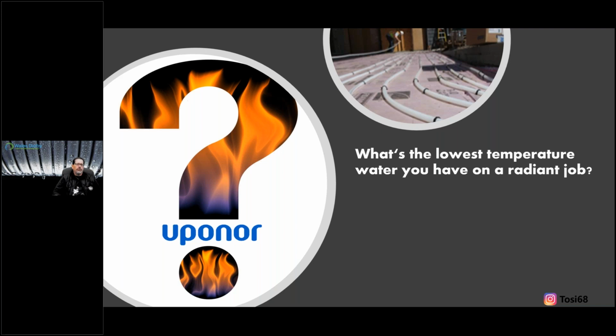So what is the lowest temperature water you have on a radiant job? Think about that, then ask yourself why I can do this water temperature here, but I don't feel comfortable forever and ever with baseboard, with panel racks, with towel warmers, with hydrocoils - grossly oversized emitters have to have more surface area. Because of that surface area, I now can use lower water temperature and still achieve great comfort. Remember, energy and comfort, that's the business. And it's going to get challenged at the next level - this is just part one, part two is coming up in a couple minutes.